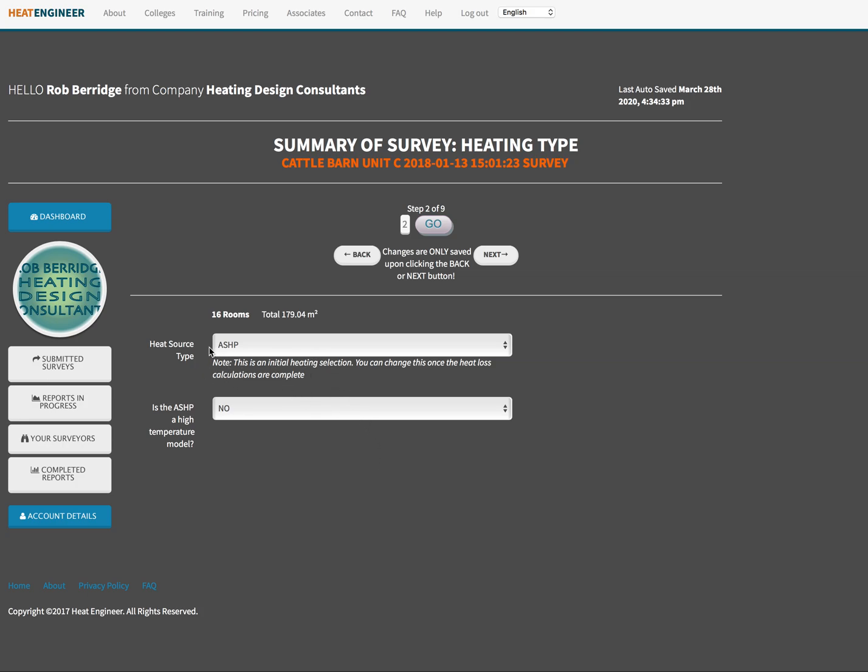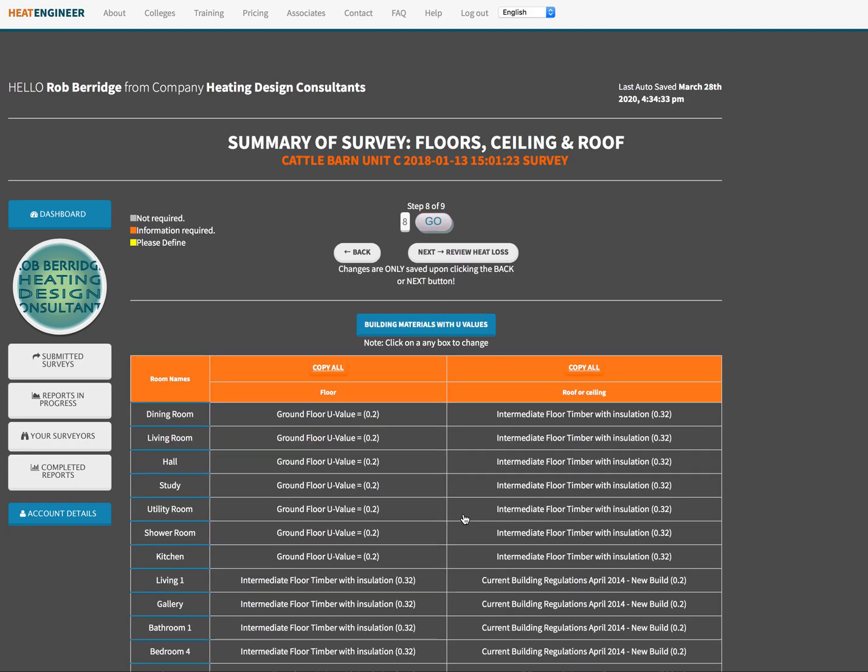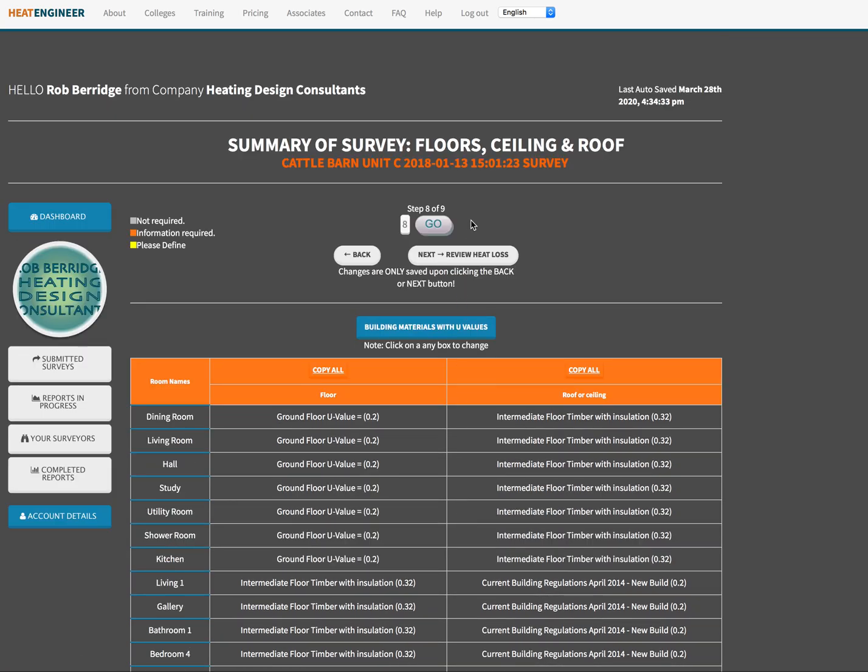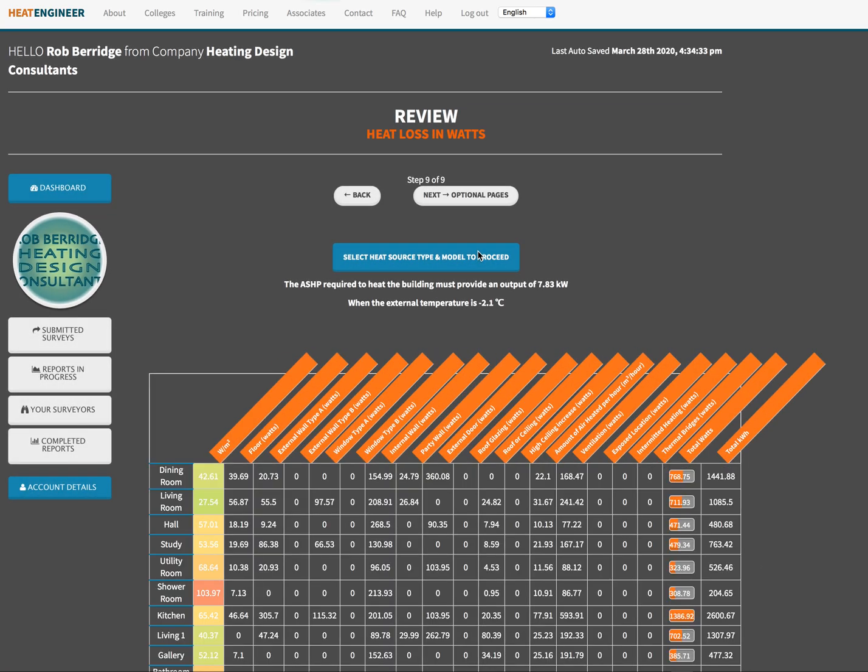This is a new project. It's an air source heat pump, a low temperature model. We're trying to keep temperatures as low as possible. So I'll just run through to the flow calculator so we can start to get some ideas of what flow rates we're going to need for this particular project. Let's get to our heat loss of what we need for this project - quite a well insulated property, fairly new build, 7.83 kilowatts, 16 rooms.